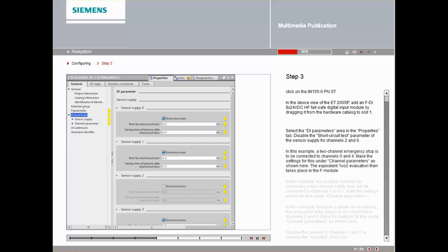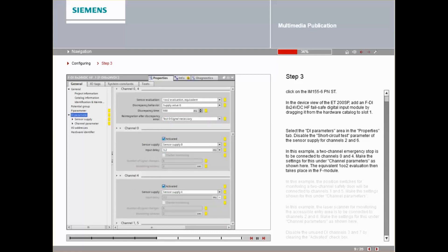In this example, a two-channel emergency stop is to be connected to channels 0 and 4. Make the settings for this under Channel Parameter as shown here. The equivalent 1 out of 2 evaluation then takes place in the F module.